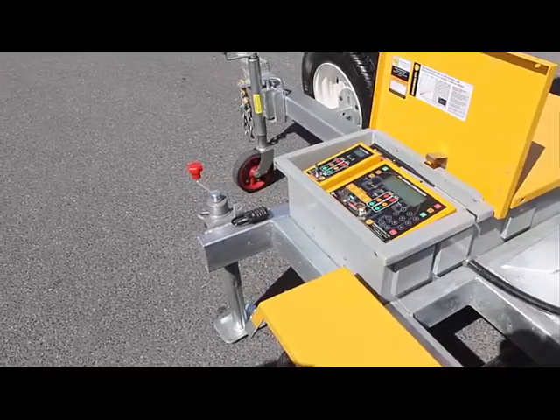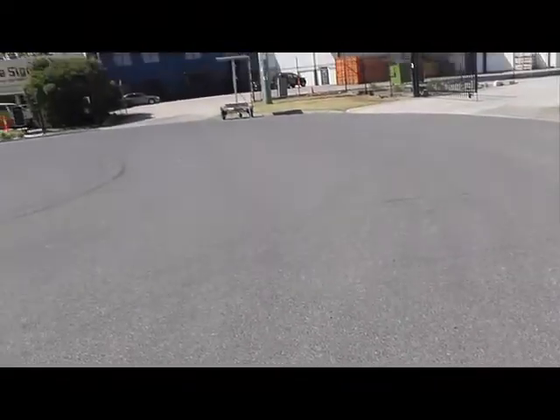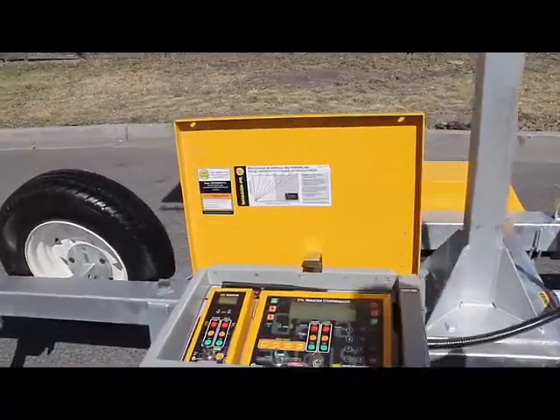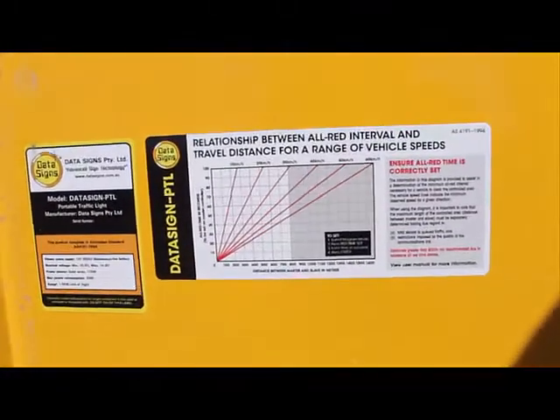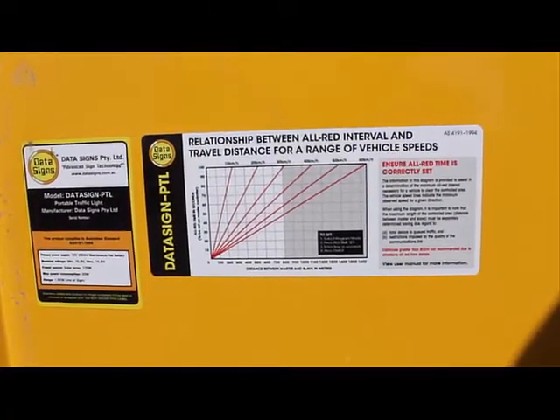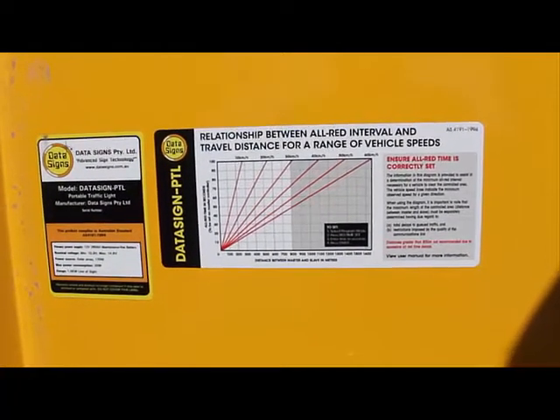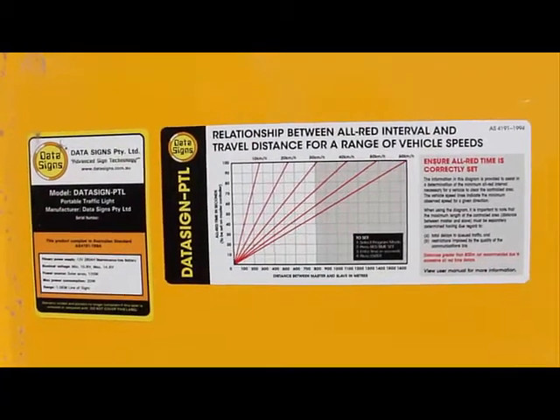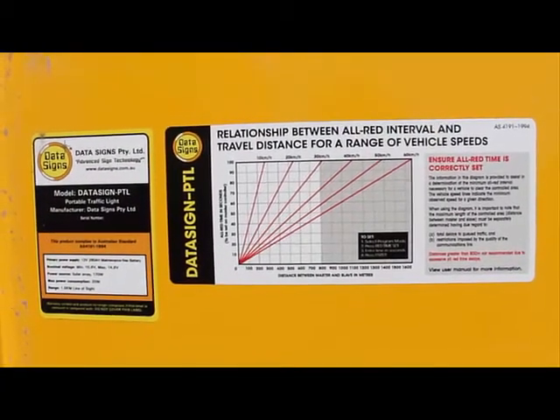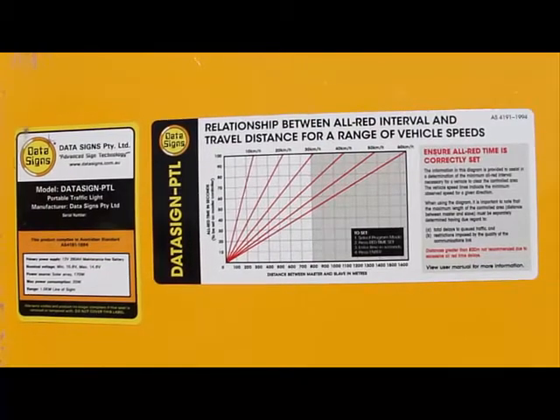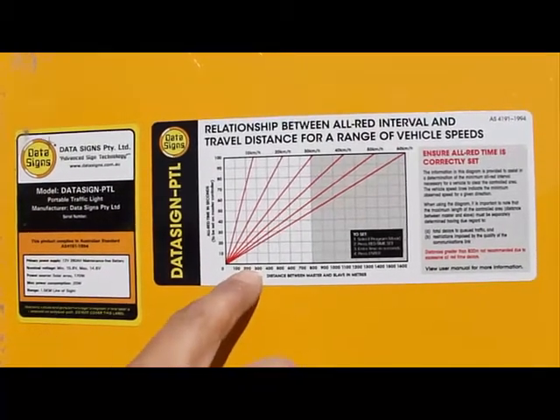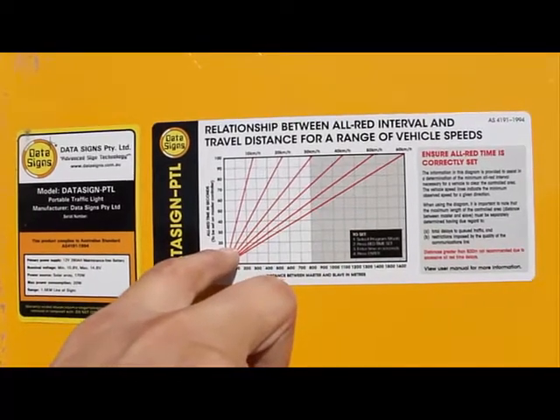To set the all red time, start by determining the distance between the master and slave. Refer to the chart inside the control box lid, taken from Australian standard AS4191, which uses metres as the unit of measurement. Based on the current speed limit set on the roadway, find the recommended all red time to set. For example, at 200 metres apart with a 40km/h speed limit, set the all red time to about 15 seconds. Press the all red button to set this.